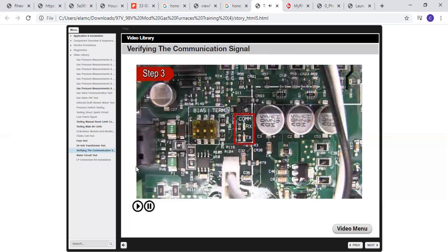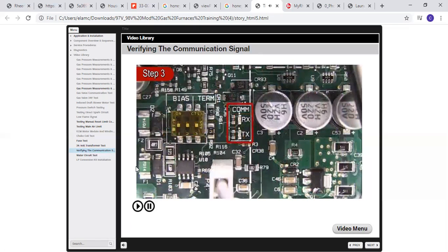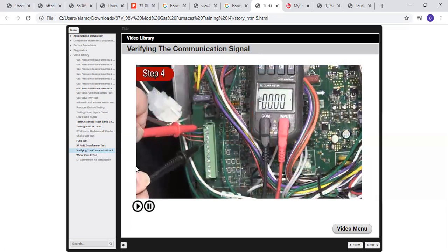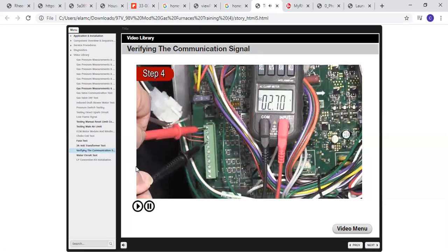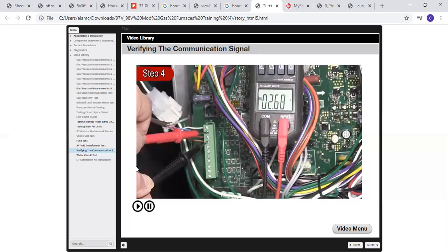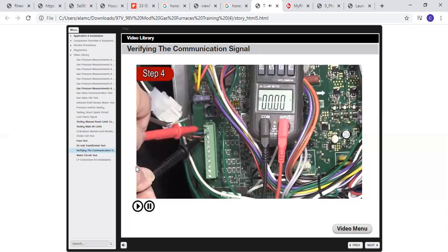Step 3. The green and red LEDs of the furnace will flash to indicate when the unit is transmitting or receiving a signal. If the LEDs are not flashing, there is no communication between the furnace and the other components of the system. Check the wiring and connections. Step 4. If there is a loss of communication to the furnace, there will be a steady voltage of 2.7 volts DC on terminals 1 to C and 2.7 volts DC on terminals 2 to C. Between terminals 1 and 2, 0 volts DC will be present.